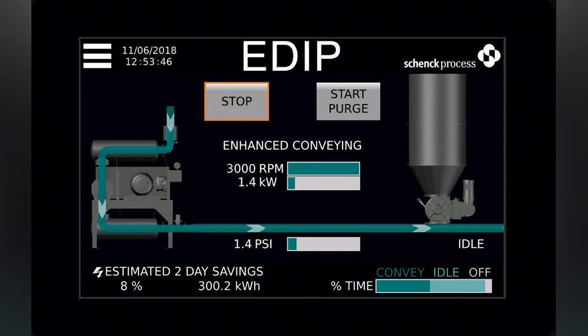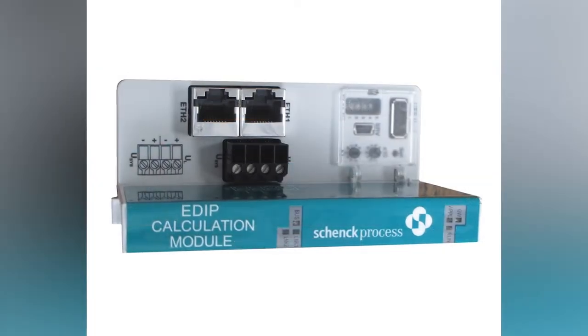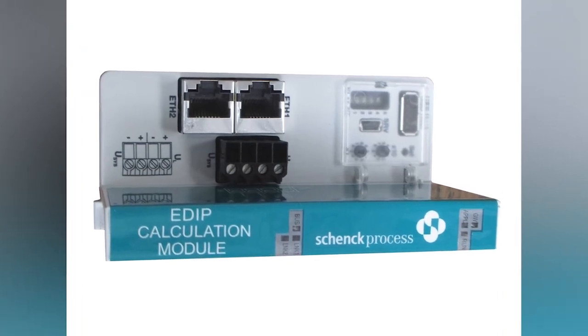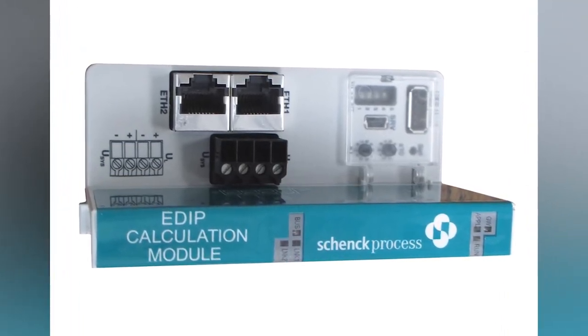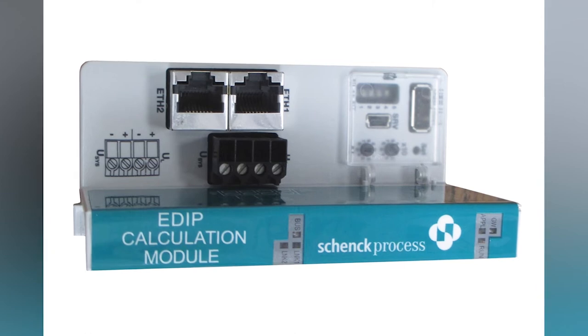The development of an algorithm to direct the blower speed changes all this. The EDIP controller takes in real-world information about the system, such as line size, blower characteristics, and convey pressure from a transmitter to set the blower at the ideal speed.